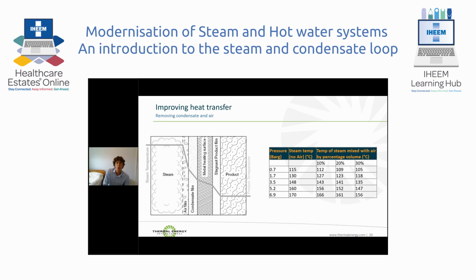The function of the steam distribution system is to deliver the steam dry to the point of use with no air. The reason we don't want air is that it is a very effective insulator. That's why we use it in the thermos flask and double glazing. Compared to the typical heat transfer coefficient for the heat exchanger wall, its thermal resistance is 1,500 to 3,000 times greater. Water is also an effective barrier to heat transfer when you've got a condensing system, of a magnitude of 100 to 150 times.